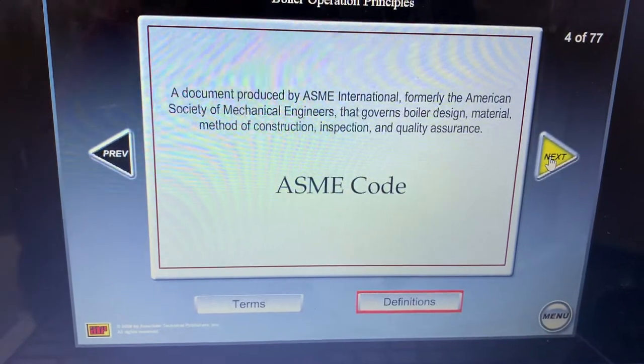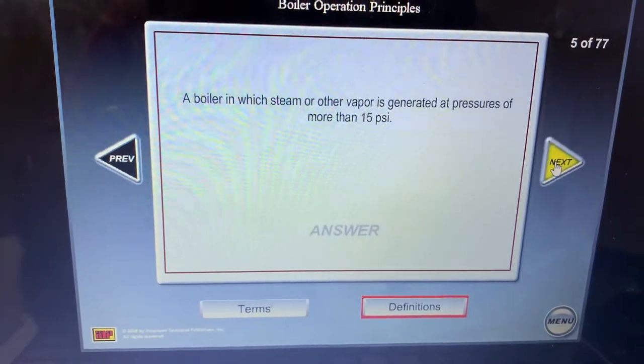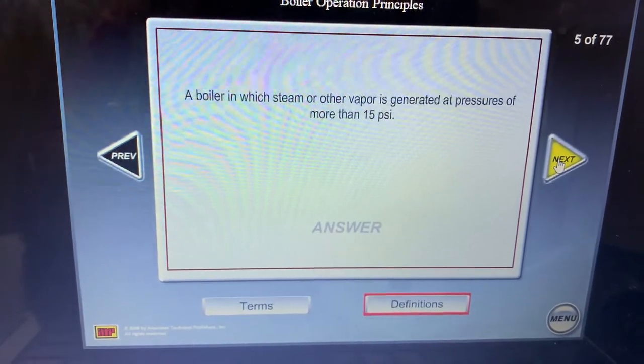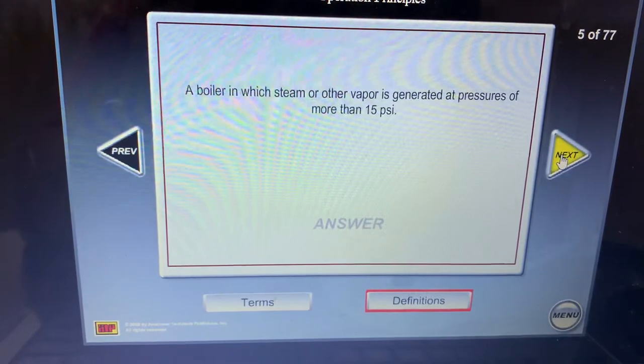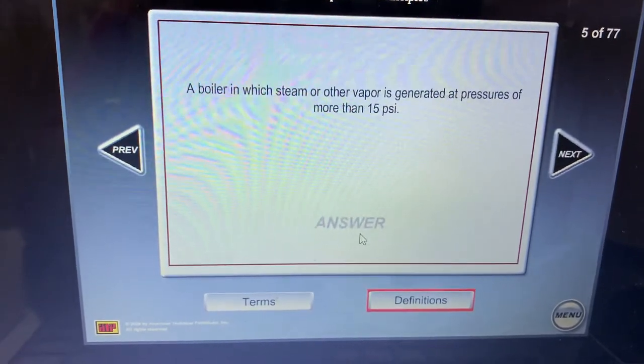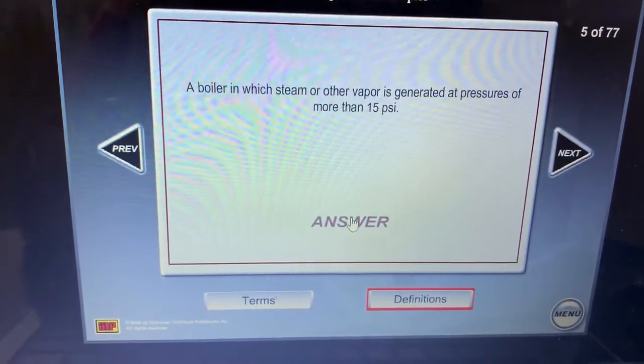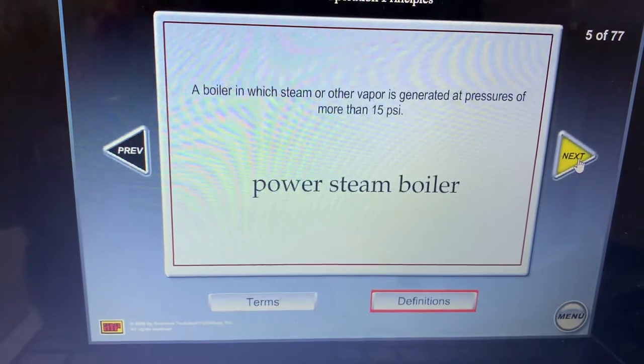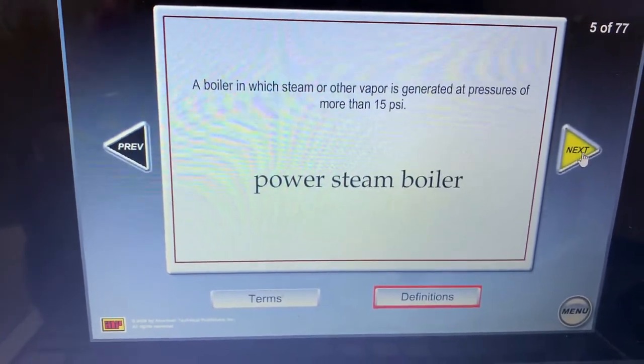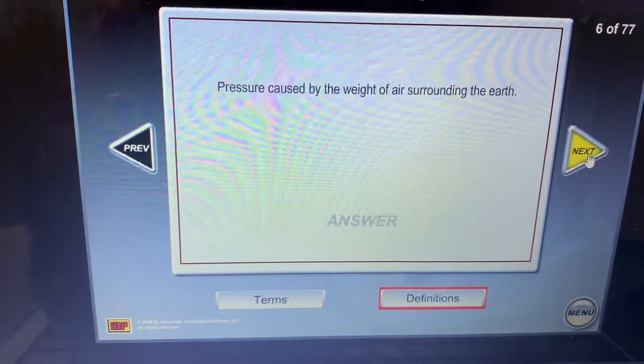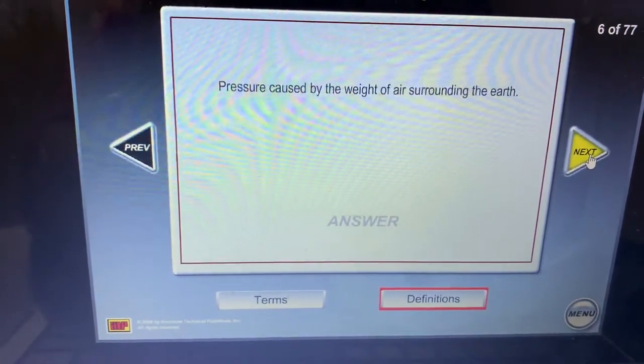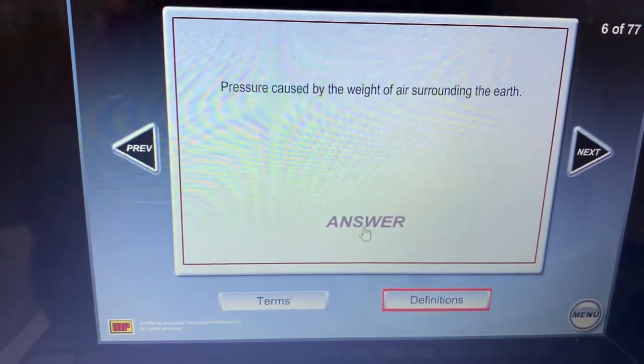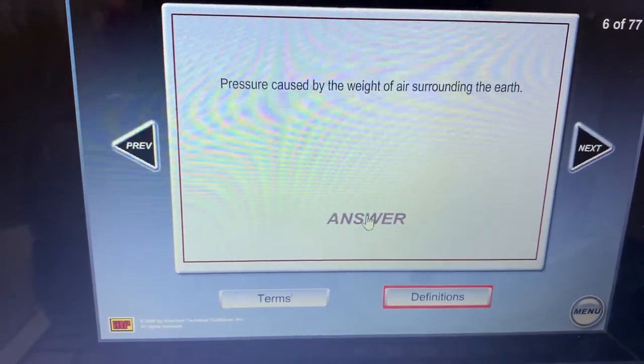For the higher license, that's very important. A boiler in which steam or vapor is generated at pressures of more than 15 PSI is a high pressure boiler — a power boiler or power steam boiler. Lower than 15 PSI is a low pressure boiler. Pressure caused by the weight of air surrounding the earth is atmospheric pressure.